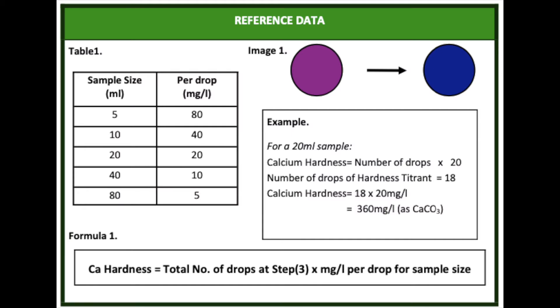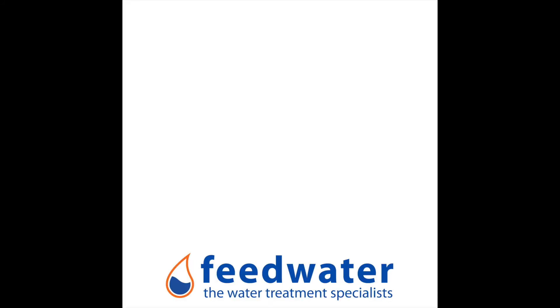Using the formula on the method sheet, calculate the calcium hardness concentration. For a 20ml sample, each drop represents 20 ppm of calcium hardness. For example, if the test took 18 drops, then you would multiply 18 by 20, which would give a calcium hardness level of 360 mg per litre.